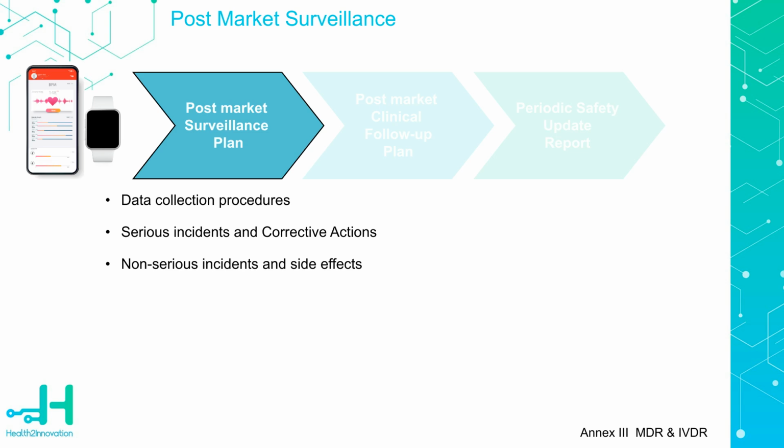Document all non-serious incidents and any unwanted side effects. Follow the complaint handling and risk management procedures within the QMS. This includes minor issues reported by users, like occasional false alerts that aren't a major health risk, and the steps taken to resolve these issues.